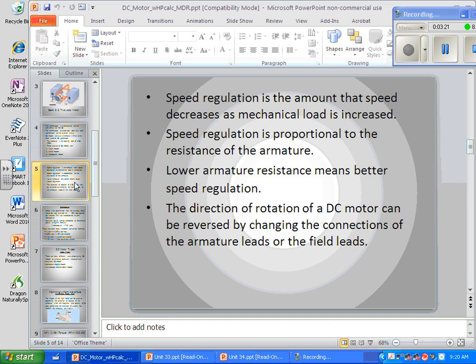Lower armature resistance means better speed regulation. The direction of rotation of a DC motor can be reversed by changing the connections of the armature leads or the field leads, but not both. If you switch both, it's going to run the same way.